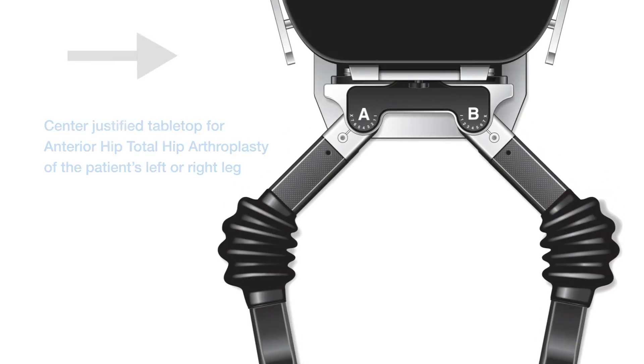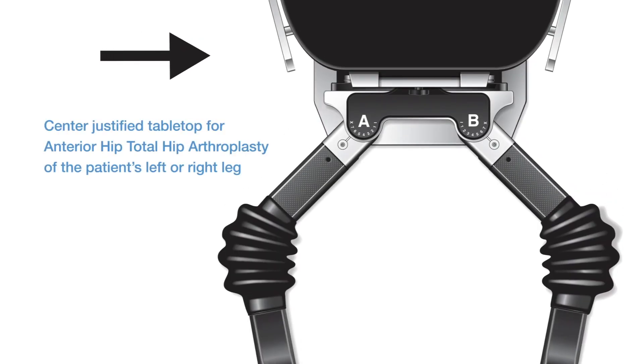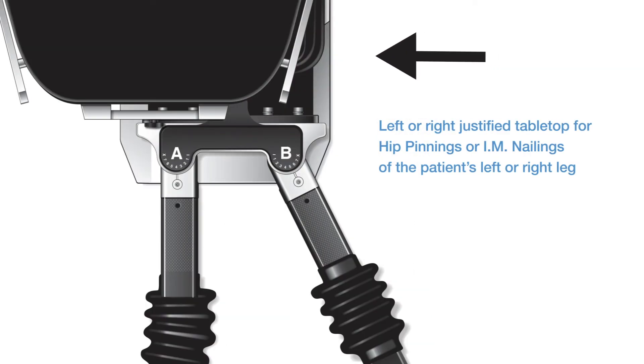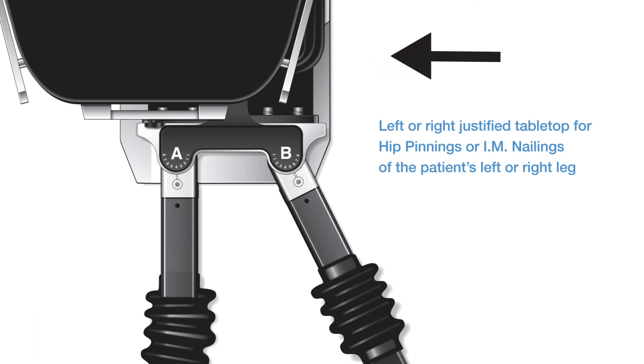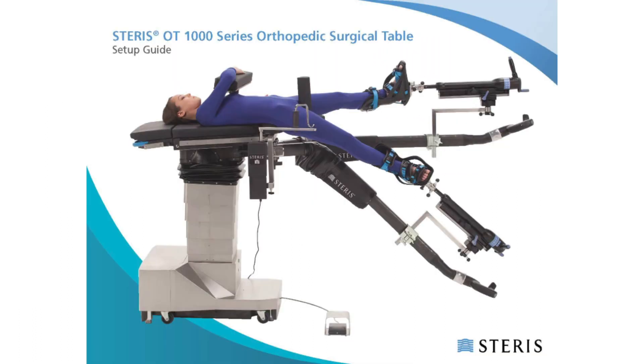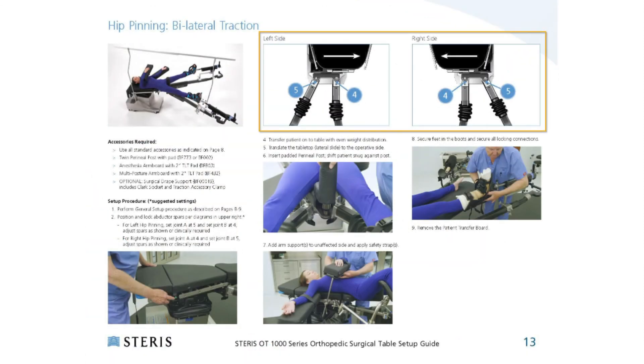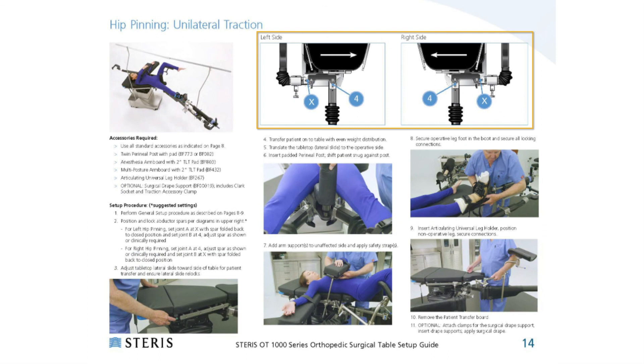The centered position is typical for anterior hip cases, whereas left justified or right justified positions are typical for an operative left or right leg fracture or trauma procedure, such as hip pinnings or IM nailings. Refer to pages 8 to 21 of the OT Table Setup Guide to verify the appropriate tabletop slide position shown in the illustrations.